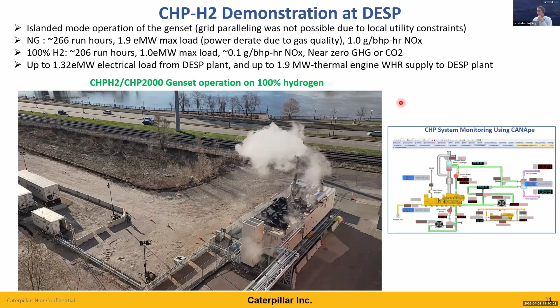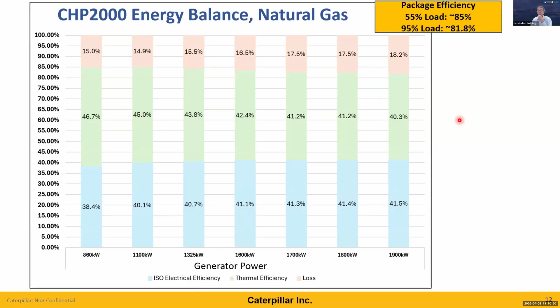Here is an example of when we ran our genset. This is natural gas only operation. We ran it from 860 kilowatt load all the way up to 1.9 megawatt load. The blue portion of the bar is the ISO electrical efficiency, the green portion is thermal efficiency, and these are the losses. Electrical efficiency was 38.4% to 41.5%, and thermal from 46.7% to about 40.3%. At 55% load, overall efficiency of the package was about 85%, and at 95% load, it was about 82%.